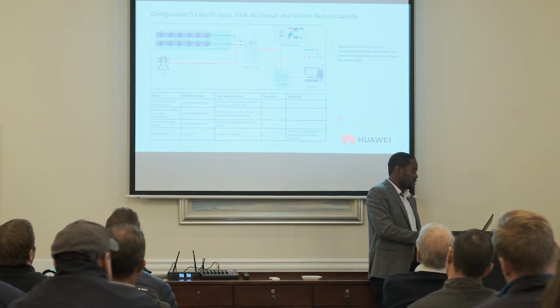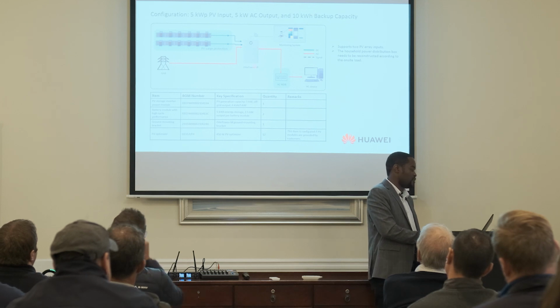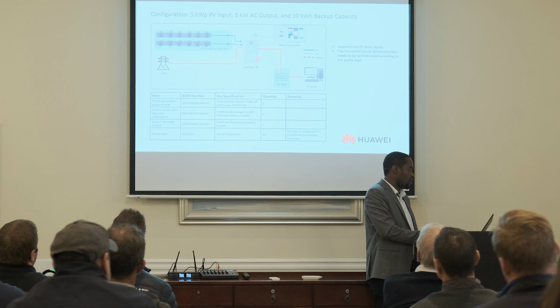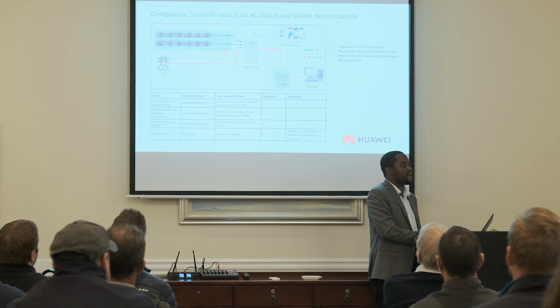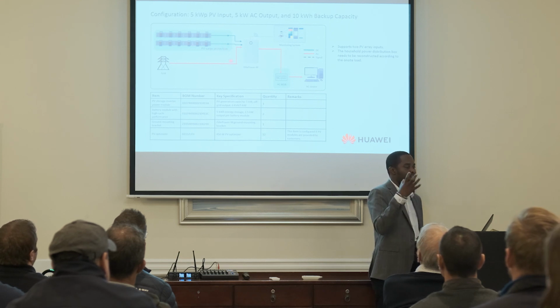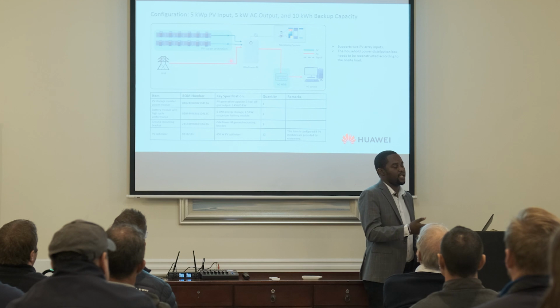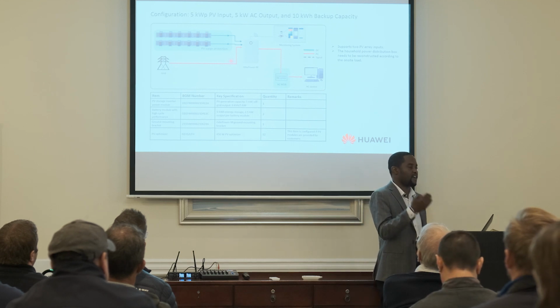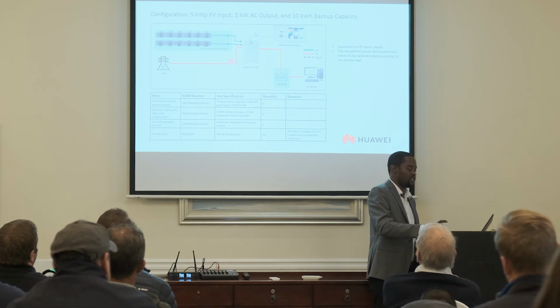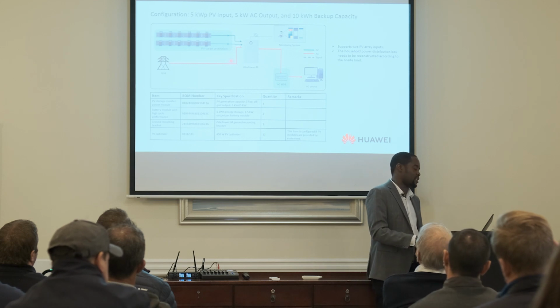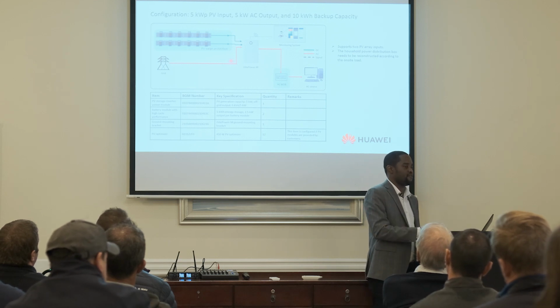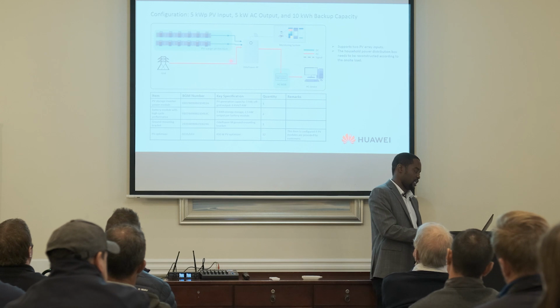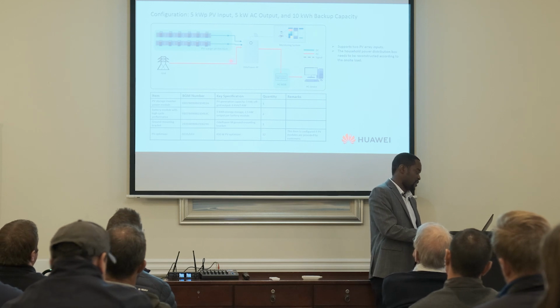Then your system will look like this. If you've got, let's say, one system, one power module, and we've got 2, 3, or up to 6, then you've got your grid input and your AC output, right? Then your PV strings cannot exceed 5,000 watts effective power. So when you are stringing, make sure you don't exceed 5,500 watts. Actually, you've got a 10% allowance, so you can only go up to 5,500 on your strings. You cannot exceed that, right?